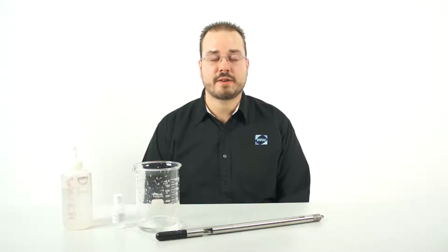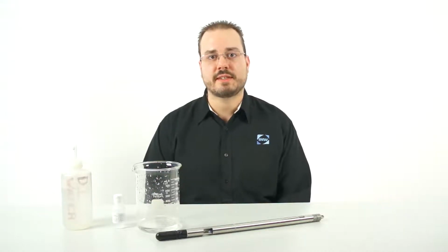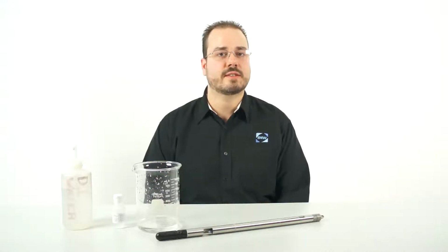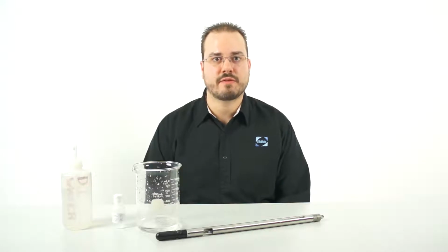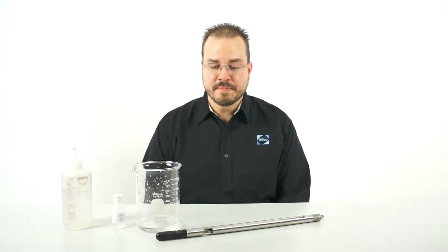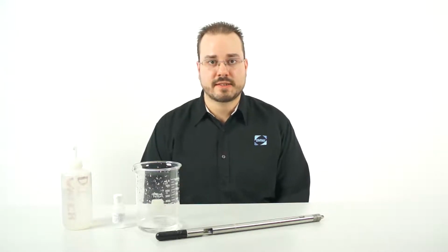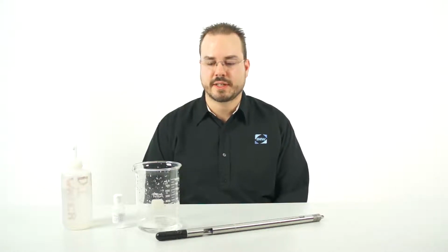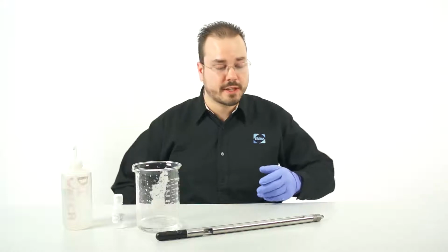Over time and deployment, the reference electrolyte will deplete. Typically we see a 3 to 6 month lifespan for the reference electrolyte, depending on location. What you'll see as the reference depletes is the data starts to show drift or erratic jumping, and then you'll know it's time to change out the electrolyte.